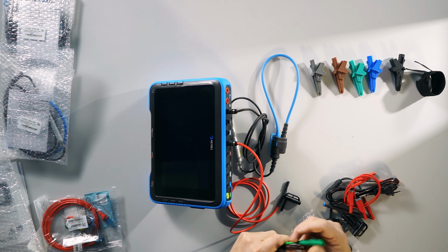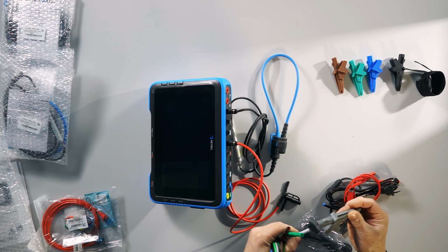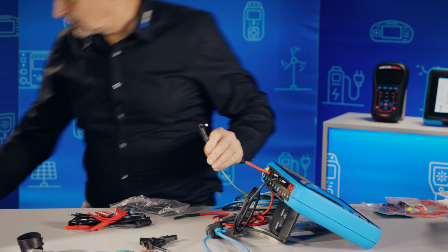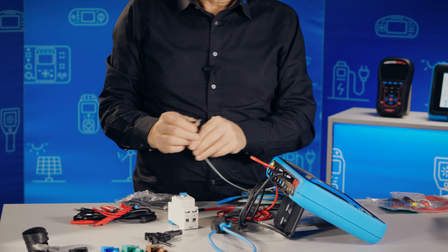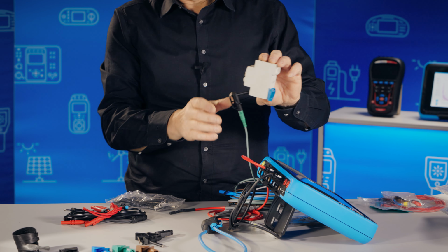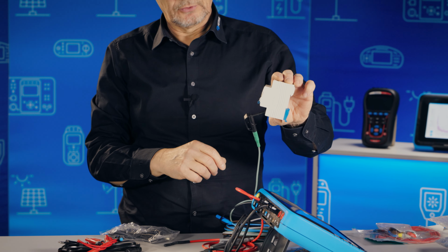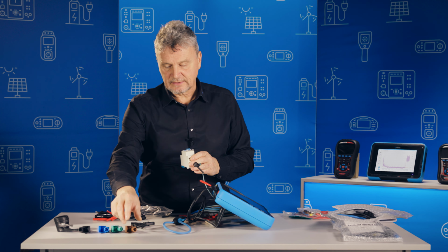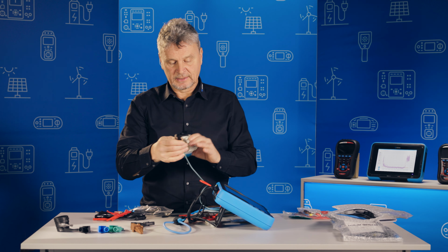To attach the voltage to a distribution board or transformer station, we have crocodiles, so you can attach directly to the nut. Additionally, we also have 5 magnetic test tips, which are very useful when you need to connect, for example, to a distribution board, to an RCD or to a fuse, when there is no place to connect a crocodile. So this is the magnetic test tip.